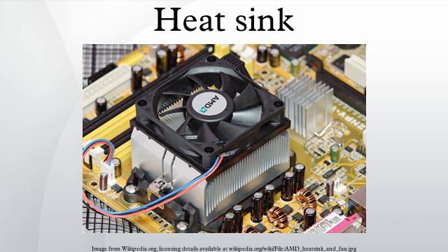In this case, finned heat sinks operating in either natural convection or forced flow will not be affected significantly by surface emissivity. In situations where convection is low, such as a flat non-fin panel with low airflow, radiative cooling can be a significant factor. Here the surface properties may be an important design factor. Matte black surfaces will radiate much more efficiently than shiny bare metal in the infrared spectrum. A shiny metal surface has low effective emissivity due to its low surface area.